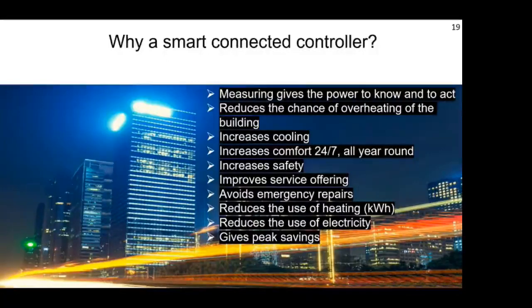By using a smart controller on a heat station, you get a better idea of how the building's performing. You design brand new buildings within an engineer's life, but you can't control what goes on in the building once you've handed over to your client and the client runs the building. You'd be quick to say that this building's not working efficiently, but with a smart controlled heat station, potentially it could outperform what was expected. And the most important thing is avoiding overheating, and the more control you'll have.